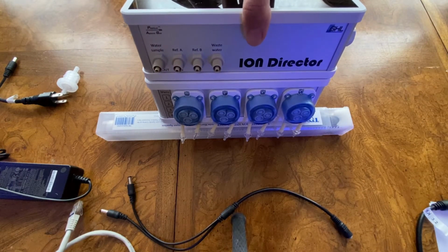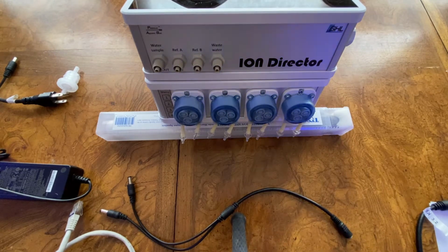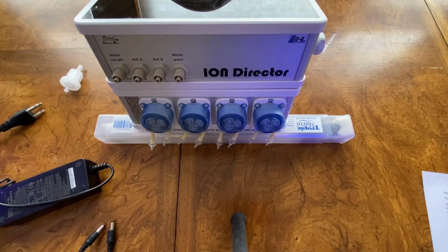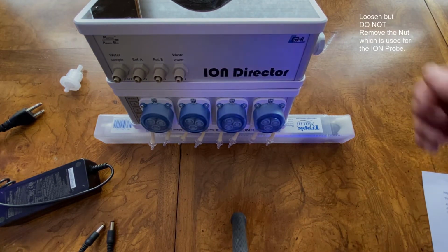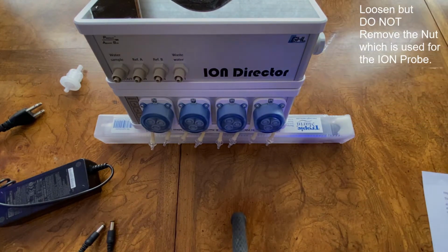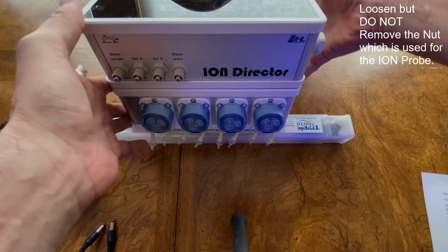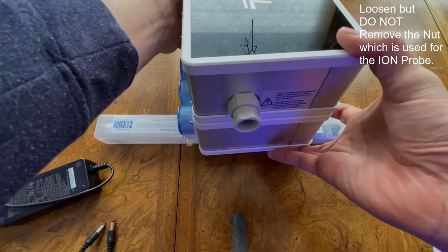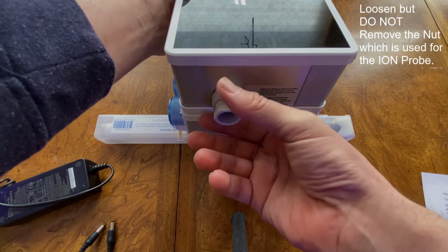Now that we know how we are going to install the Ion Director and the doser, we now need to install the ion probe. It is very important that you install the probe correctly, because incorrect installation will cause false readings of the unit. First, you need to loosen the nut on the side of the Ion Director. Loosen, but do not remove.